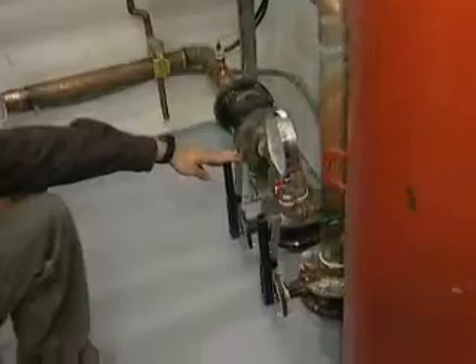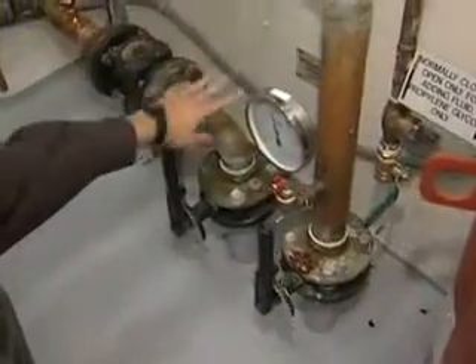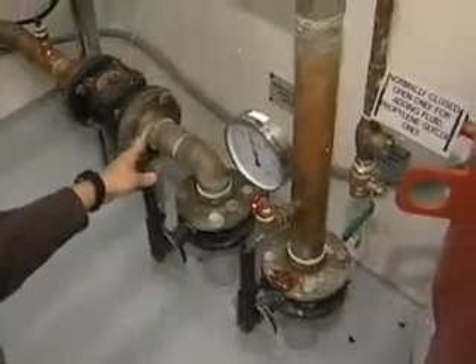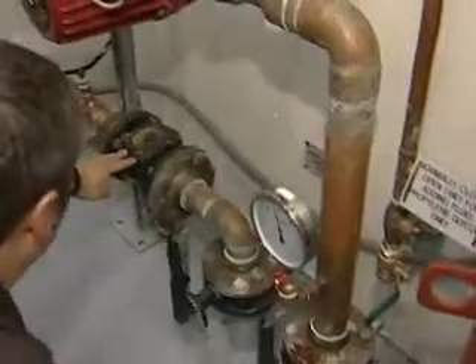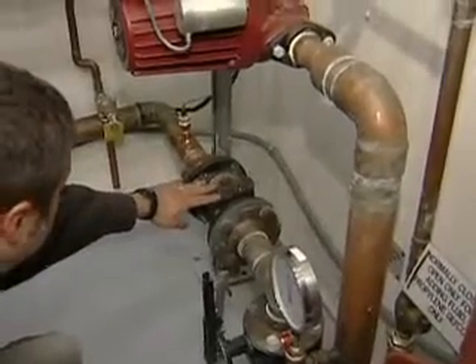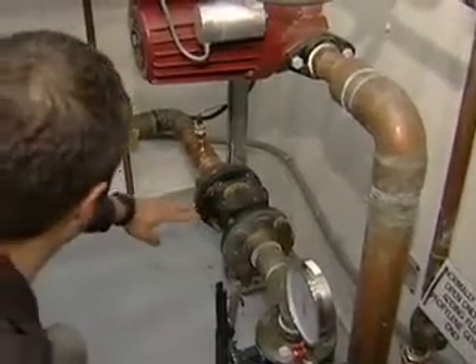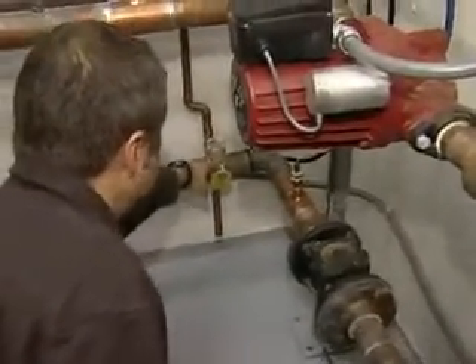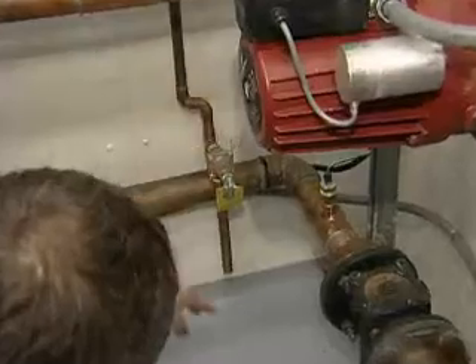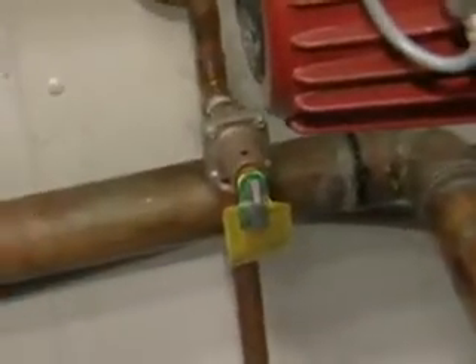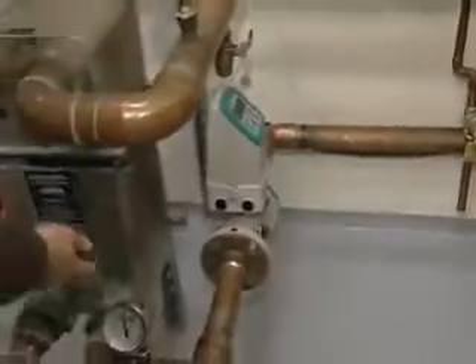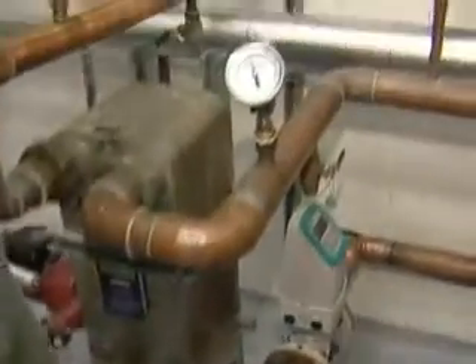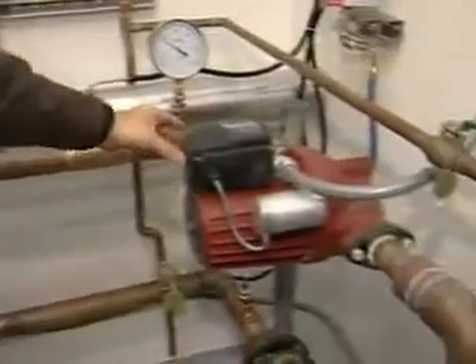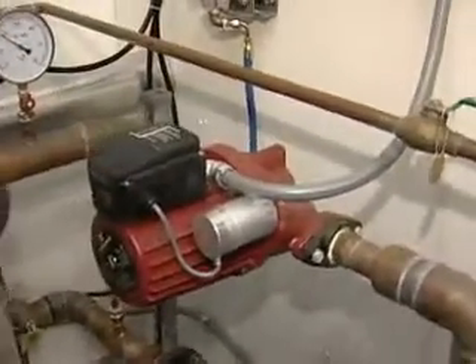So we'll go through some of the components in the typical system. So here we come through the floor. We have our main isolation valves where we go out of the building. And these valves are labeled normally open, waste heat supply, waste heat return. We come through a strainer here. This takes out any metal particles that could be in the piping system to keep them from clogging up the heat exchanger. Over here we have a pressure relief valve. This device, if we get overpressure on the system, will relieve and it'll spill glycol to the floor. And then we come around here, we have thermometers so we can monitor the temperature coming in and going back out. Pressure gauges. Now one thing I want to point out is on each pump we've installed a pressure gauge upstream and downstream, and that's how you tell that your pumps are operating.